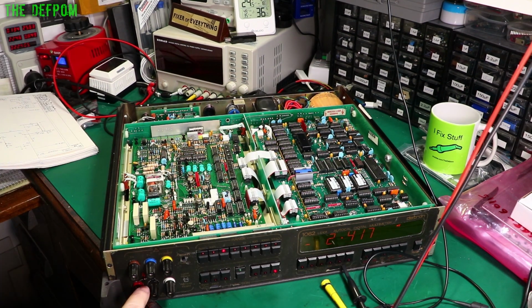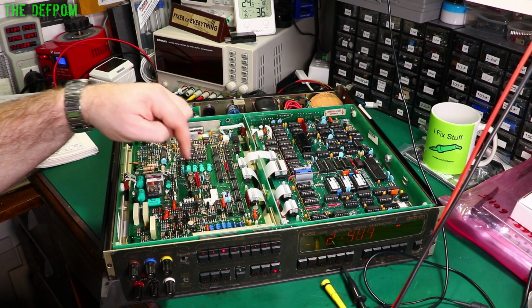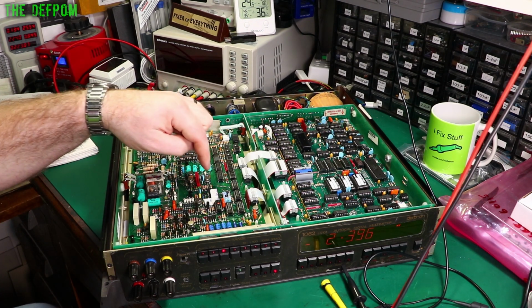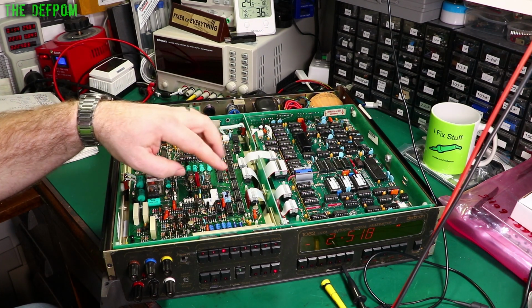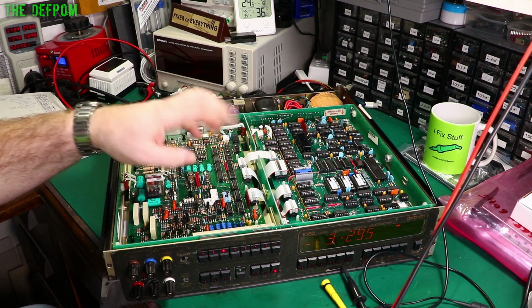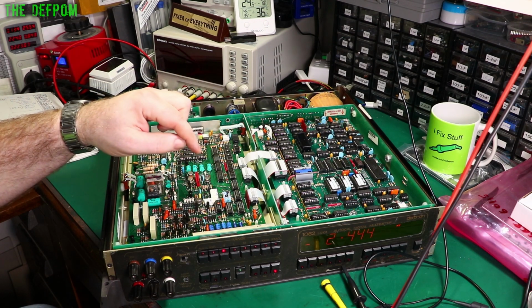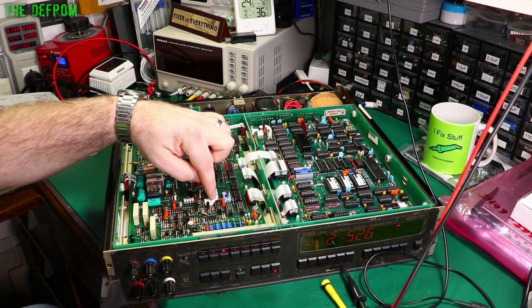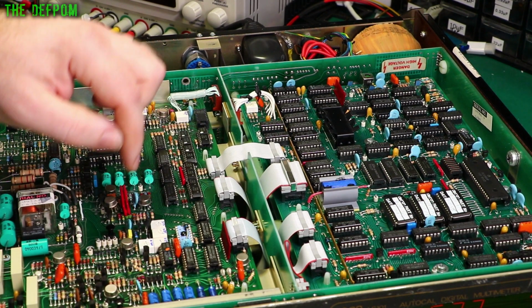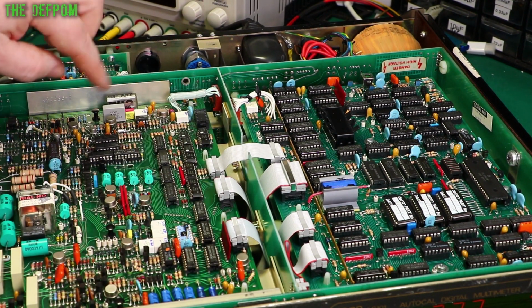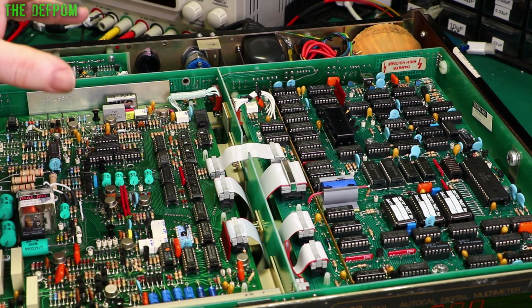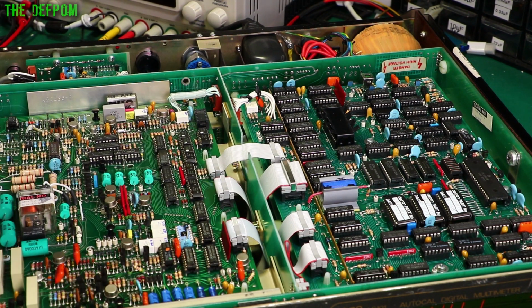Right, so the next step is to stick a 10 mega ohm resistor across the input on here, DC volts, 0.1 volt scaling, and I've got to adjust some things over here to do the adjustment. So apparently I've got to center a couple of the adjustments already here and then set R159, which is this one just here. R159 is right there. I've already gone through and marked a lot of these adjustments, so it makes it a little bit quicker to try and do the adjustments. And okay, obviously that one there, that one there, so I can look it up and figure it out. As well as some of the test points.